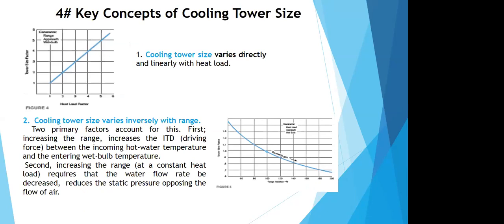So we start with the first slide with the recap of four key concepts of cooling tower sizing. The first important concept about the cooling tower size is that if you have a wet bulb approach constant, and if you increase the heat load of the process, whether it's the heat load of a building or the heat load of industry, then the cooling tower size will vary directly and linearly with the heat load.